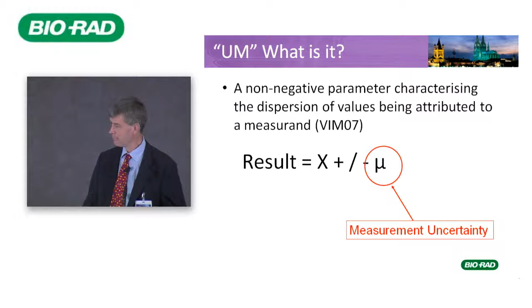However, I think there are two concepts that we've got to deal with when we're talking about communicating our results with doctors. That's the uncertainty of the measurement. And in Australia, our requirements under ISO 15189 to calculate that, to estimate that, it says very specifically it is the uncertainty of the calculation of the measurement that we perform in the laboratory. And that is one very important concept. The different concept is, and I've put it in this rather long-handed way, it's the uncertainty of our result as an estimate of the homeostatic set point for the analyte in a patient.